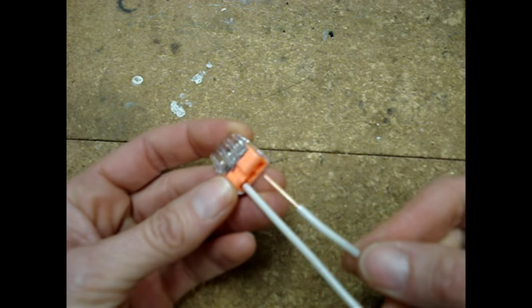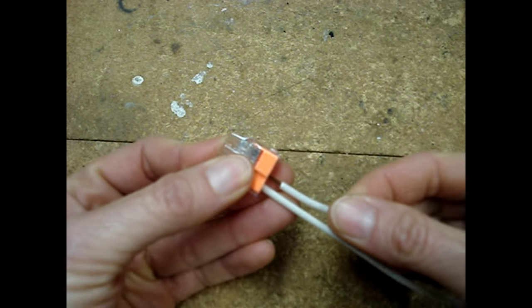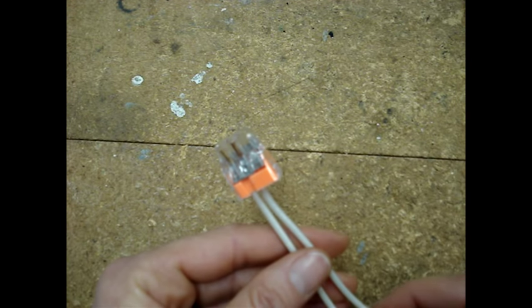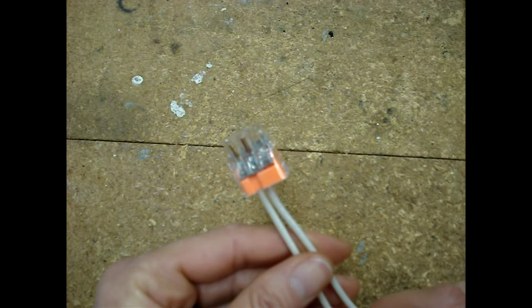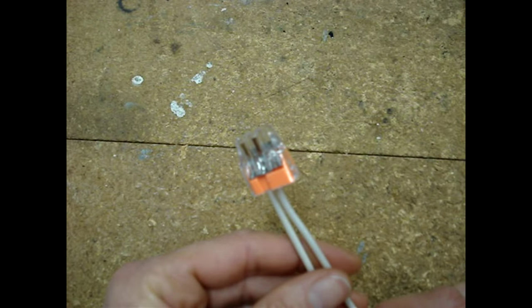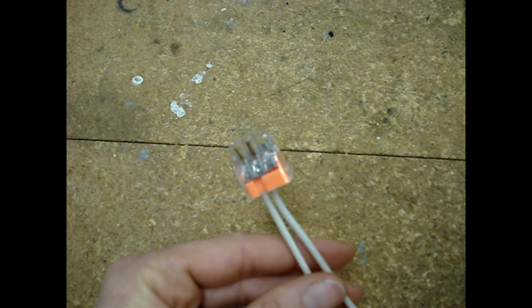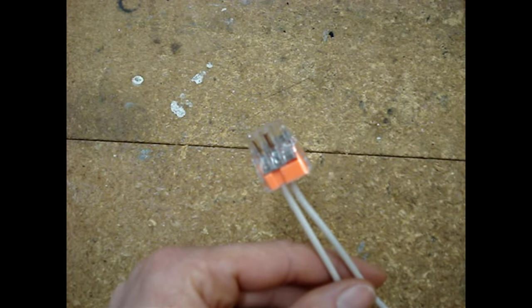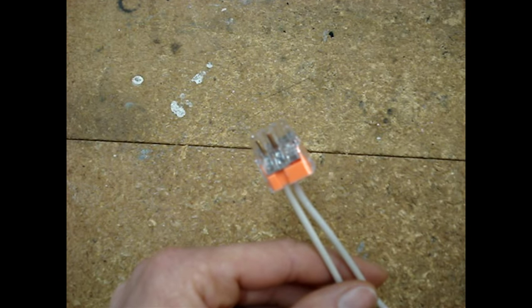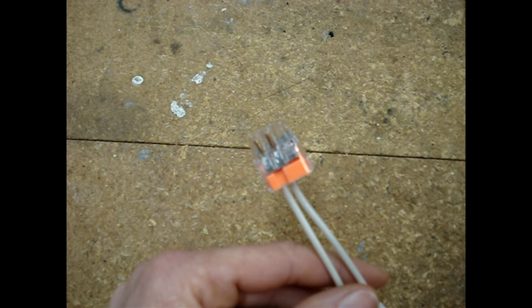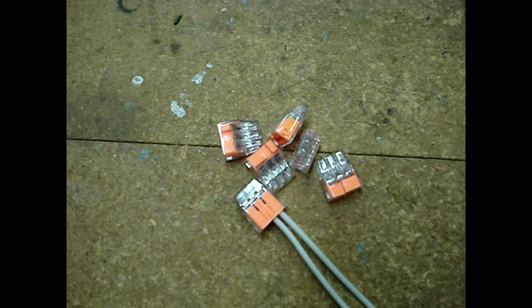If used properly, I think they're okay. They have their place. You may not have the hand strength to twist multiple number 12 wires together. It's a faster way to make a connection. I'd be scared to reuse these connectors multiple times. I definitely wouldn't use them with stranded wire or with a circuit that's going to be taken apart and put together a lot. You'd have to keep on cutting your wire back and you'd eventually end up with very short wires.